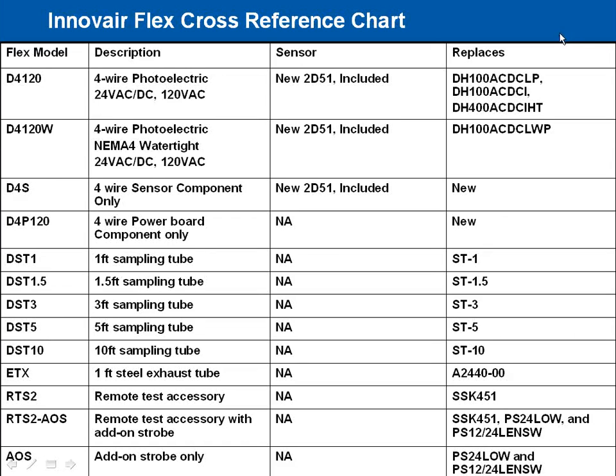And on the right-hand side, the right column, it tells you what it replaces. It's the old System Sensor model numbers. And like I said, unfortunately, the sampling tubes are not compatible between the two, really. So you would need a new sampling tube if you buy a new detector. But some of the accessories are directly compatible.